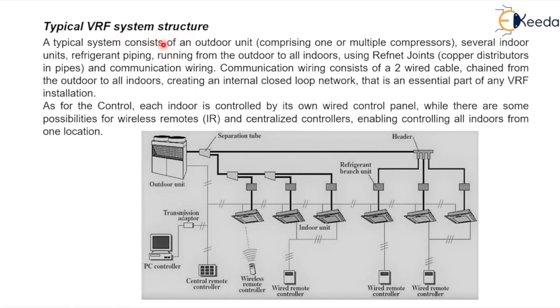A typical VRF system consists of an outdoor unit comprising one or multiple compressors, several indoor units, refrigerant piping running from the outdoor to all indoors using refnet joints (copper distributors), and communication wiring consisting of a two-wire cable between outdoor and indoor units creating an internal closed loop network. In this diagram, you can see six indoor units connected to one outdoor unit, with refnet joints used to branch the piping.